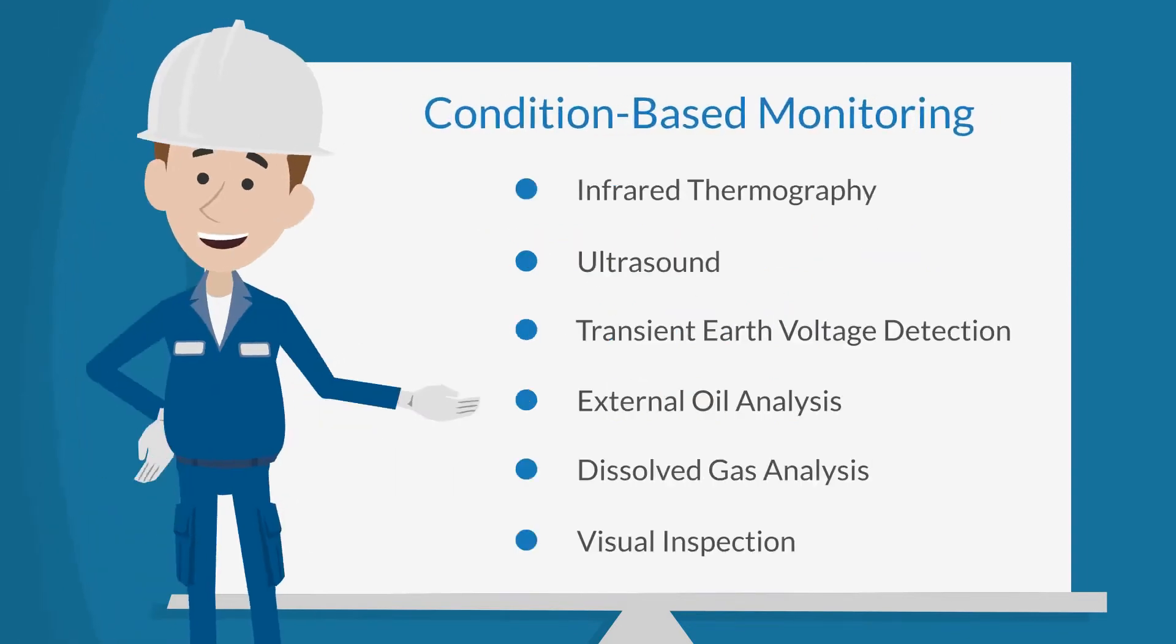These technologies include infrared thermography, which detects loose connections, crimps, and cable creepage. Structure-borne ultrasound, which detects loose windings and other mechanical faults. Airborne ultrasound, which detects arcing, tracking, and corona.